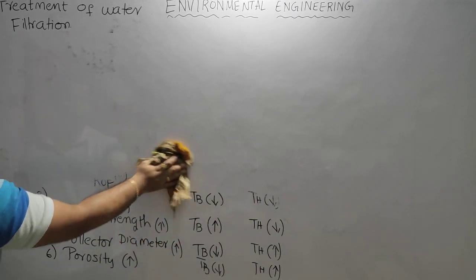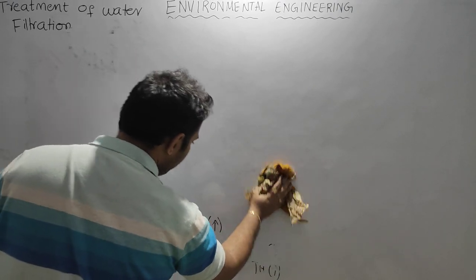If we properly clean the filter within the stipulated time, whenever it raises the alarm, that is when the head loss reaches 90% of the total head of the water, or when the filtered water turbidity is more than 2.5 NTU, then many problems can be avoided. The major remedy for operation problems in the filter is proper cleaning of the filter.